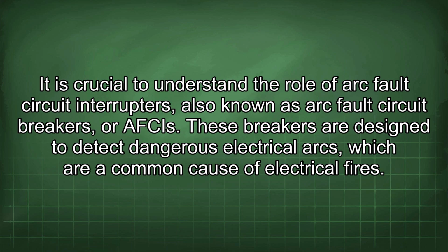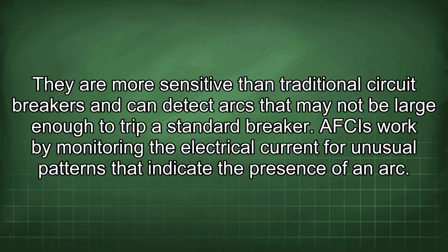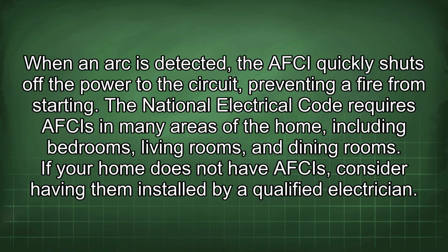These breakers are designed to detect dangerous electrical arcs, which are a common cause of electrical fires. They are more sensitive than traditional circuit breakers and can detect arcs that may not be large enough to trip a standard breaker. AFCIs work by monitoring the electrical current for unusual patterns that indicate the presence of an arc. When an arc is detected, the AFCI quickly shuts off the power to the circuit, preventing a fire from starting.